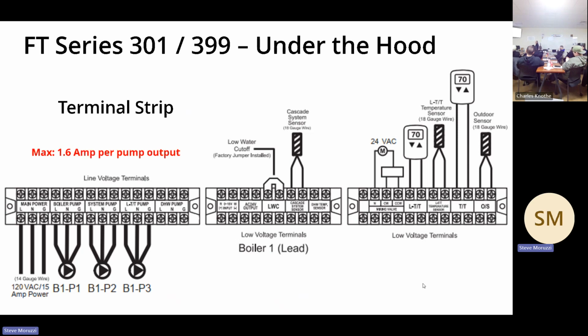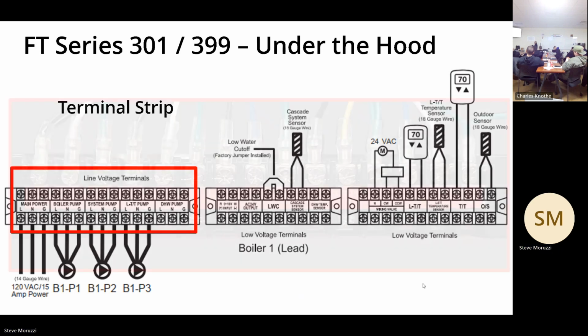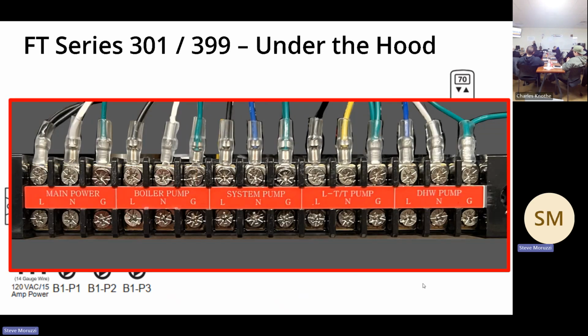And we even have, let's see if we go through this. Max output for the amperage is 1.6 amps on these. Most of us are using ECM type pumps, which are, you know, less than an amp anyways, or half amp. Terminals, let me enlarge this, here we go. So main power is coming in on the first 3 terminals. Boiler pump. We want to control the boiler pump, system pump. We can do a low temperature pump zone and an indirect pump. So all of those terminals are there.